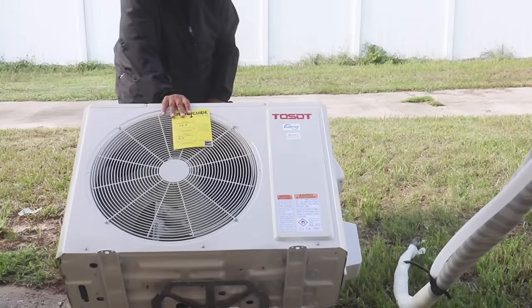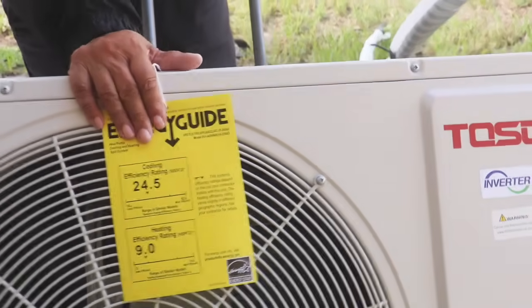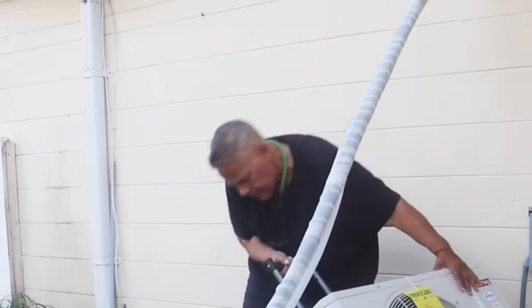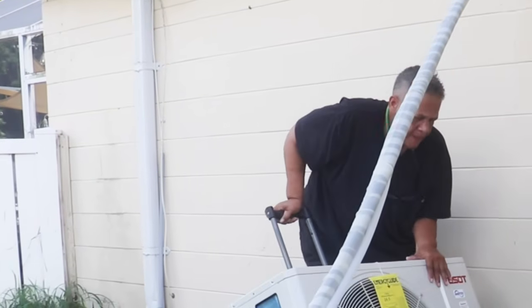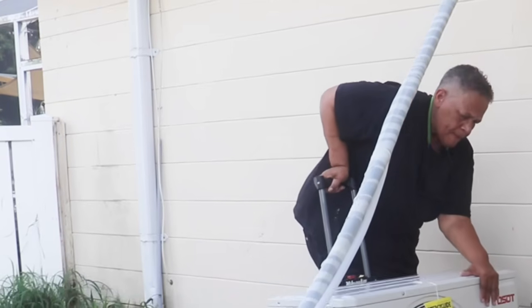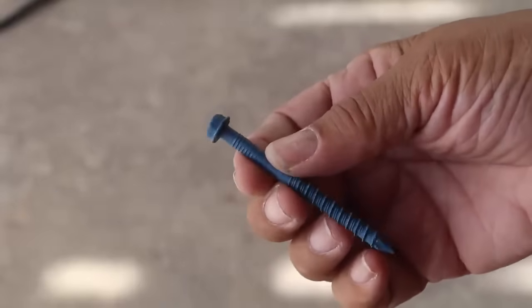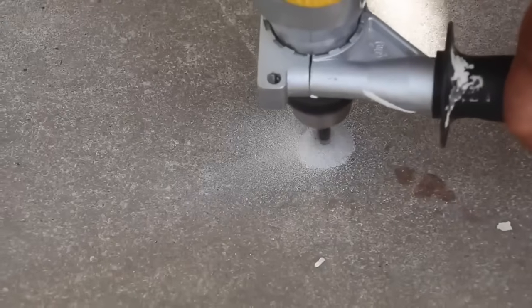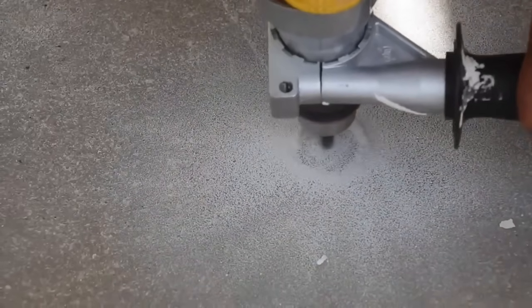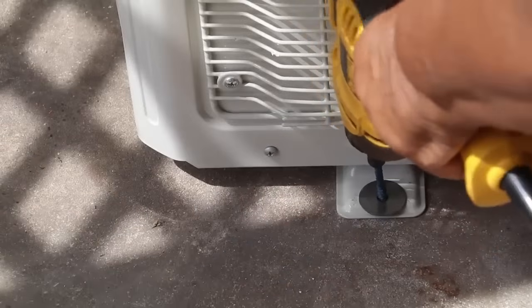Now it's time to install our outdoor unit, our condenser — and this is when the workarounds come into play, where you don't have to have expert skills but still wind up saving money with the install. First, before I get to that, we have to secure the condenser to a concrete pad. I'm doing that with concrete screws — I've already drilled my pilot holes, and that's going to give it something to grab hold of and make a secure connection with the condenser and the concrete pad.